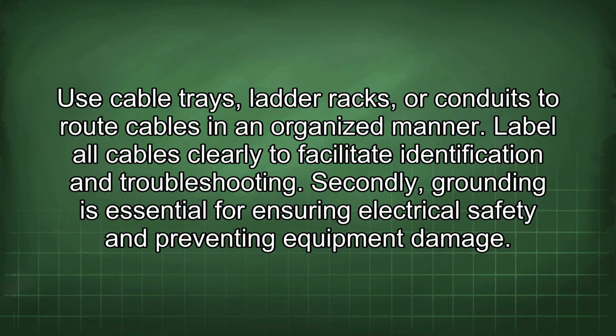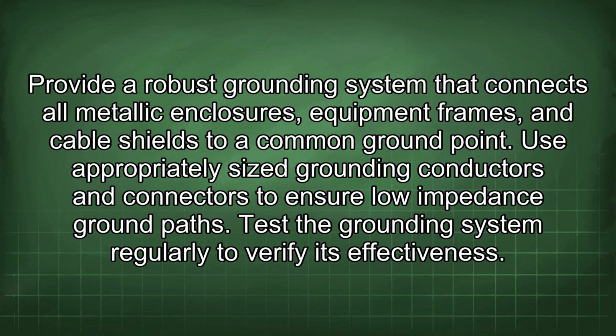Secondly, grounding is essential for ensuring electrical safety and preventing equipment damage. Provide a robust grounding system that connects all metallic enclosures, equipment frames, and cable shields to a common ground point. Use appropriately sized grounding conductors and connectors to ensure low impedance ground paths. Test the grounding system regularly to verify its effectiveness.